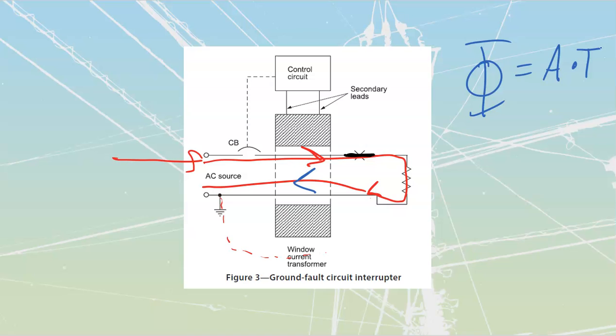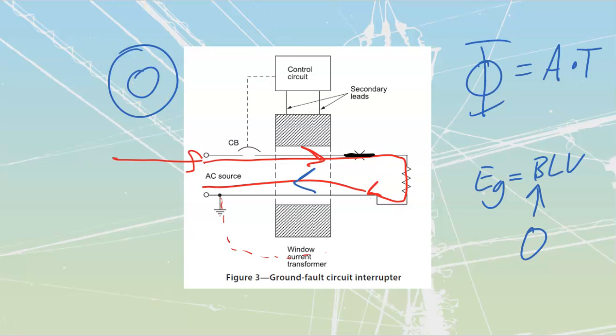So, equal amounts of magnetic flux, therefore they're going to cancel each other out, which would mean that according to Faraday's law over here, Eg is equal to BLV, I have got a net of 0, which means that the generated value of voltage should be 0. What we have over here is a toroidal type of transformer. This is a window type of transformer. We don't see that window over here, but those lines are traveling through, going out to that load, and then coming back from that load and traveling like that. So that toroidal transformer right now with 0 flux is going to have 0 volts that it's going to pick up.